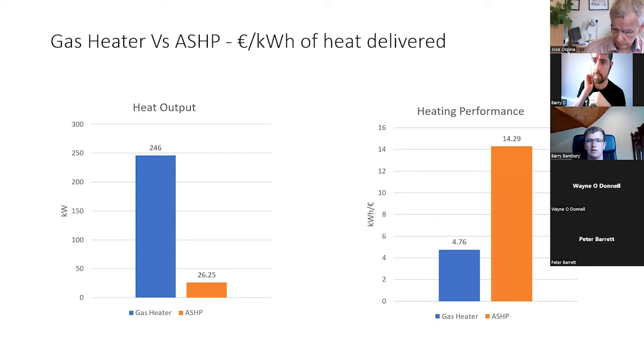So, a massive difference. One of the main reasons is the actual quantity of heat coming out of the air source heat pump. We're assuming a coefficient of performance of 3.5 for the air source heat pump. So it's only delivering around 26.5 or 26.25 kilowatts of energy to the space. Now that's very common in a retrofit solution.